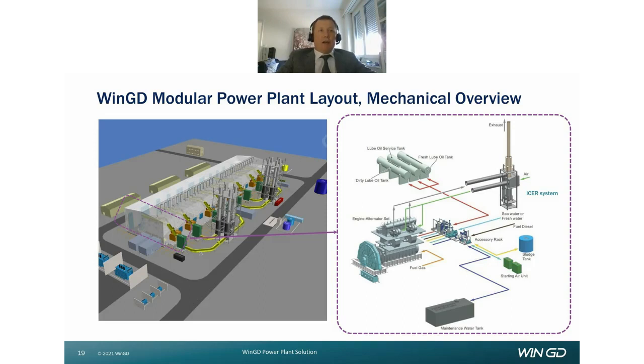Let's zoom into the modular power plant layout and see in more detail how the power module looks from a mechanical and electrical standpoint. The core of the power generation shown here is a 21 megawatt genset, which is made up of a WinGD 9X62DF engine and the relevant generator. Along with the genset, we can see the accessory rack, embedding the cooling equipment, the ICER system dedicated to the exhaust abatement, the starting receiver for the engine starting, and the centralized lubricant storage system. Of course, the genset power rating can vary as a result of the project-specific plant configuration study, but the overall concept here explained remains the same. Further on, we will review individually the most critical mechanical packages.